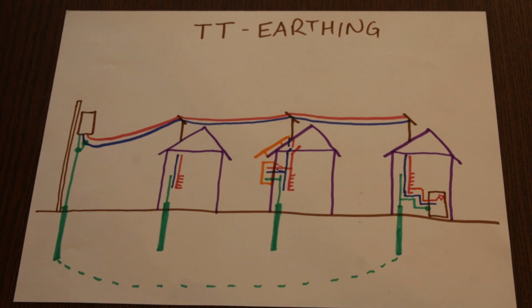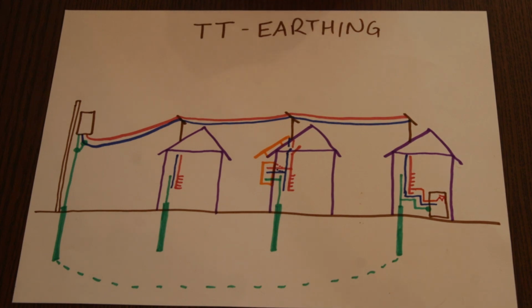Why can't we do some sort of a mixed setup? Let's say I can use TN for user number 1 and 2 maybe, and everything further away is just TT. So house number 1 and house number 2 would have a bond inside the distribution, and return currents could go via the wire, and just the other ones would go via the ground. Well, this is not possible, because we would then create parallel paths for the fault currents, which is also the problem when we are talking about installing a solar system now.